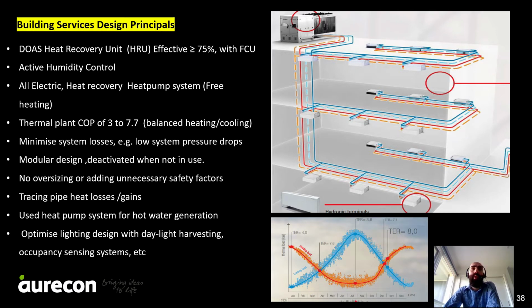Optimizing pipe work and duct work to minimize the pressure drops and system losses was the key point in the design. We also adopted a modular air conditioning system design for each space to make sure that air conditioning is provided when it's needed and it can be deactivated when not in use. Having more confidence on the building operation and less unknown in our design, we avoided using any unnecessary safety factors, so our systems are appropriately sized for the building.